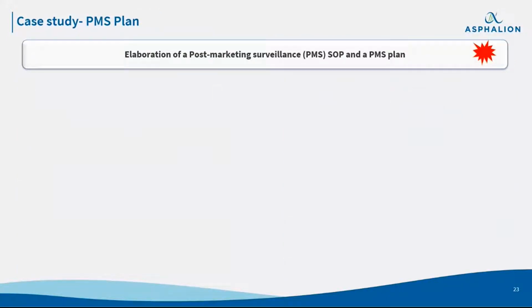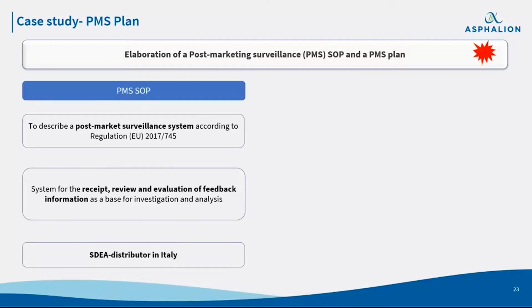So the first gap identified was the absence of a PMS SOP and a PMS plan. So we have to elaborate them. According to the SOP, the purpose of the SOP will be to describe a post-marketing surveillance system according to the new regulation. The objective will be to establish a system for the receipt, review, and evaluation of feedback information from the market. In addition, you have to take into account that the maintenance of the manufacturer's product PMS system can be outsourced to a partner through a vigilance agreement. In this case, remember, we have a distributor in Italy, so the responsibilities of both parties have to be clearly defined, and I explain this in the SOP.